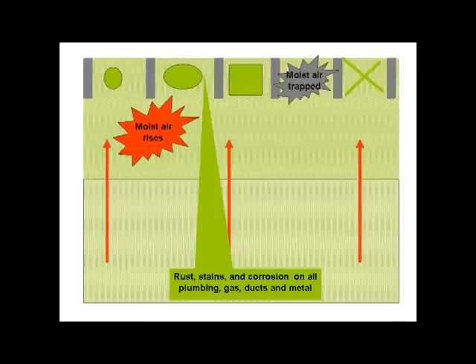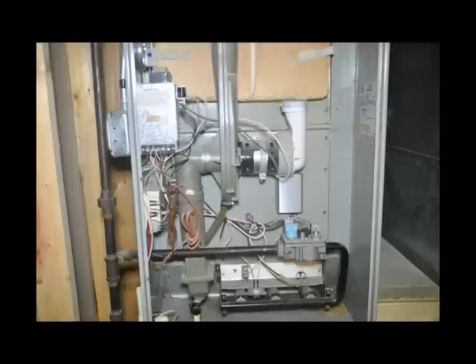Additionally, moist air is lighter than dry air, so moist air will rise up — this is why it rains. These grains of moisture rose up into the ceiling joist pockets, where humidity was higher than on the basement floor. This condition, combined with summer air conditioning cold air supply ductwork also located in the upper basement joist cavities, made the air in those upper cavities colder, and dew point condensation occurred on all metal surfaces, causing corrosion, rust, and stains.